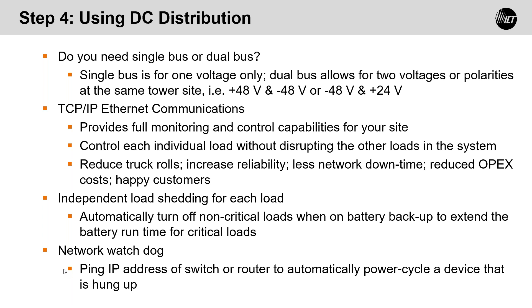We also have a feature called a network watchdog, which would ping the IP address of, say, a switch or a router to automatically power cycle that device if it gets hung up. So you know that if you lose your router, you've lost your comms. You have no ability to communicate with the site. But the network watchdog is internal between the rectifier and the device, and so it would automatically reboot that device, and you'd set up the parameters as to how much time it would take for that to happen in the outputs, in the GUI control for the distribution panel.